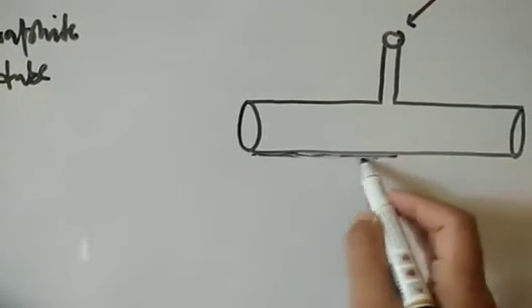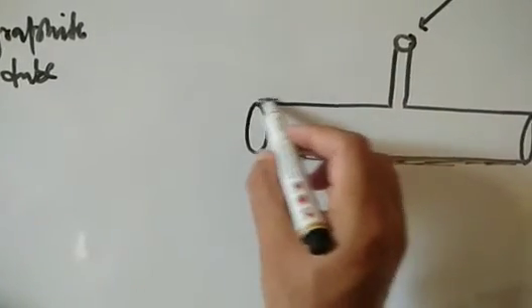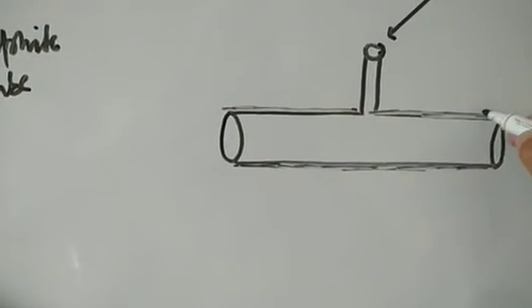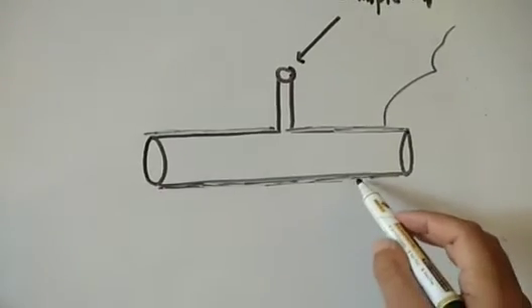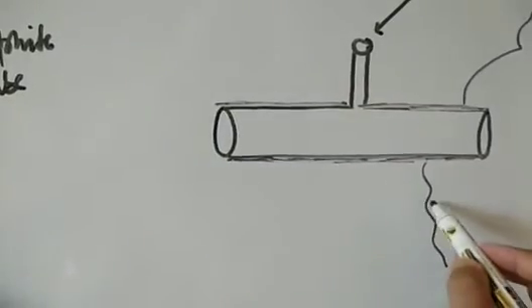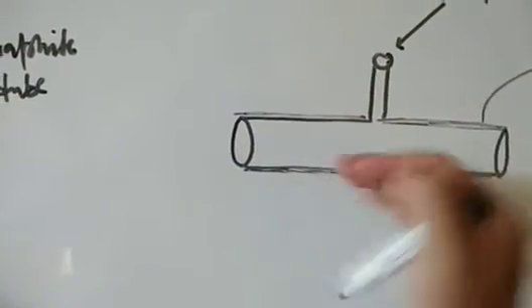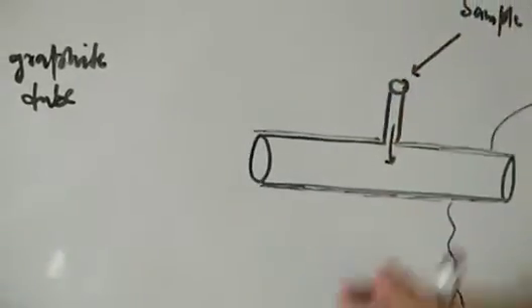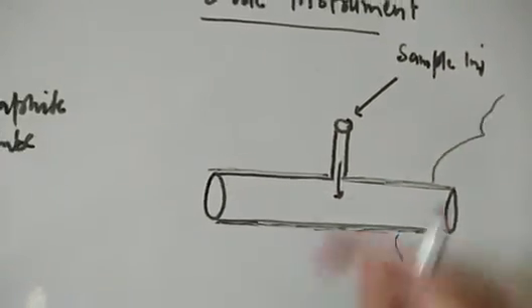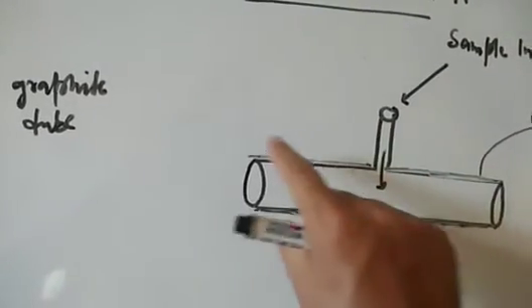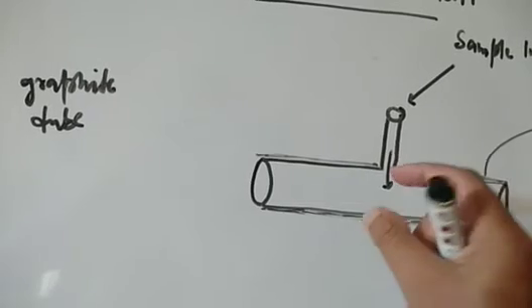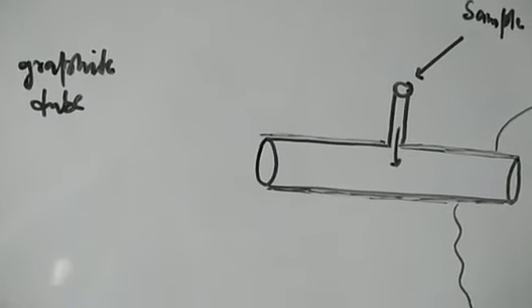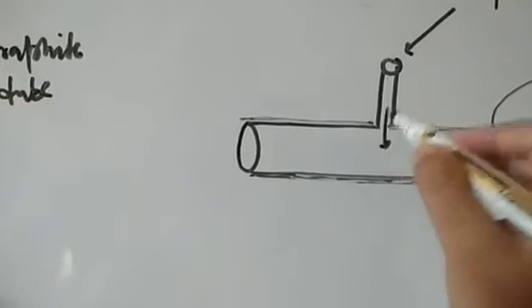The graphite tube is encased with electrical contacts. Electricity flows through these contacts, producing heat, and that heat burns the sample and converts it into the vapor state. The three heating steps happen inside the tube. The electrical setup is used to heat the sample.